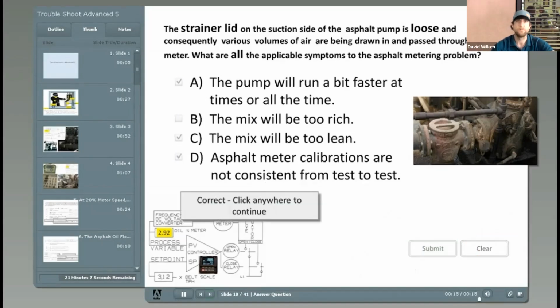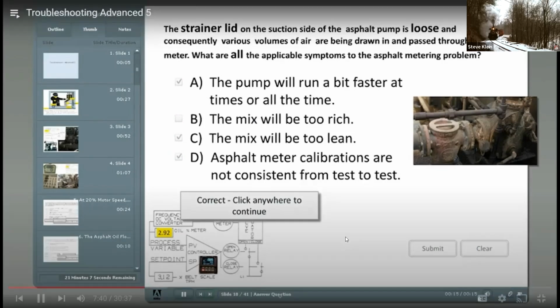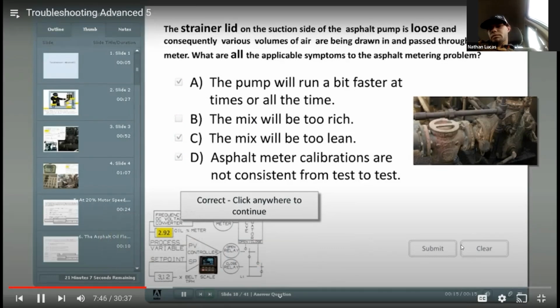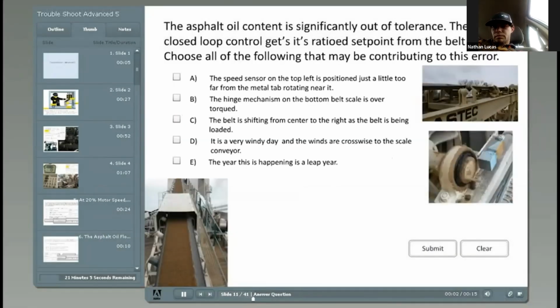The correct answers are A, C, and D. The meter will be metering air almost as if it is oil. Consequently, the meter will measure inconsistent amounts of oil. Asphalt oil content is significantly out of tolerance. The oil closed-loop control gets its ratioed set point from the belt scale. Choose all of the following that may be contributing to this error.